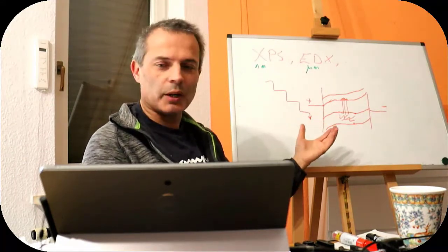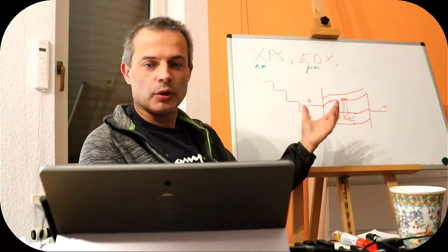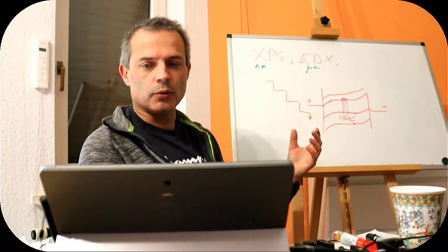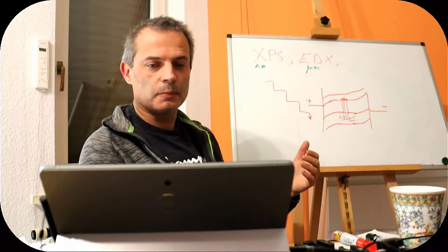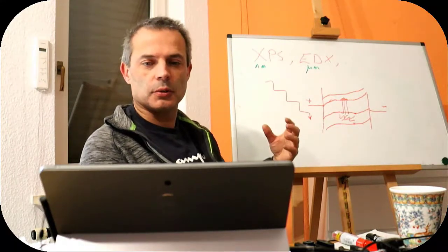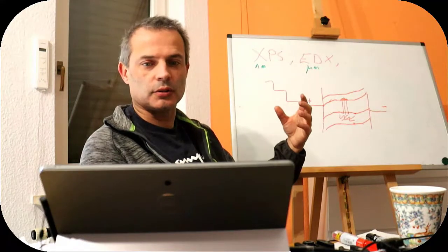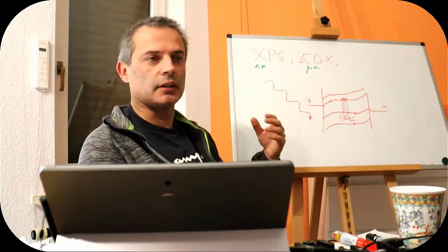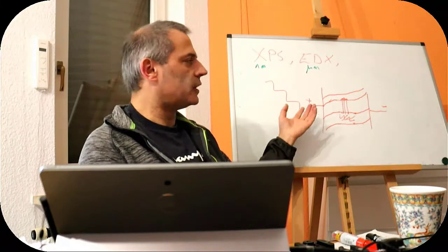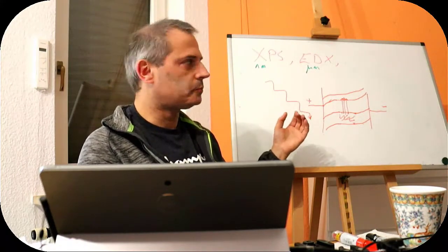So there is a running program all of the time that is looking for double, triple and quadruple the energy, typically just double, and it rejects measurements that are exact multiples of each other, because that is usually a sign that two photons have hit at the same time.